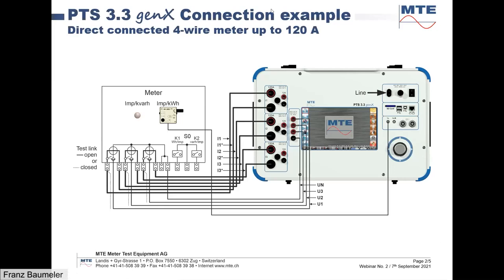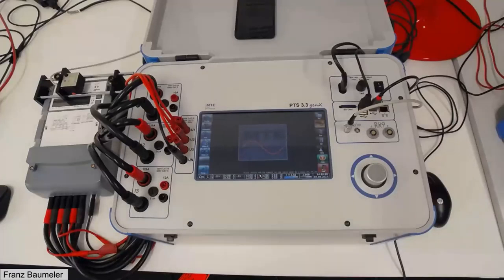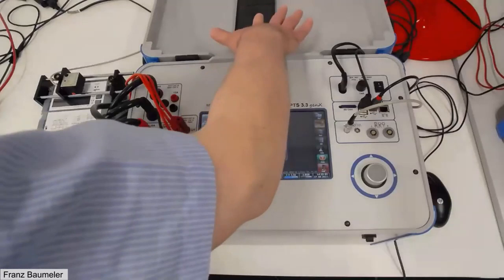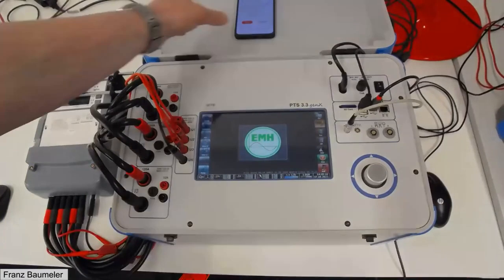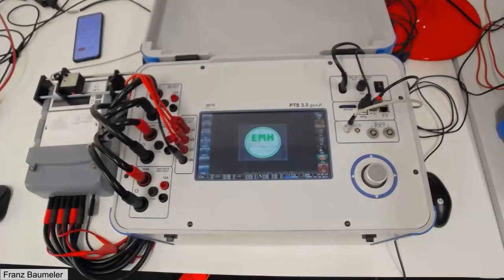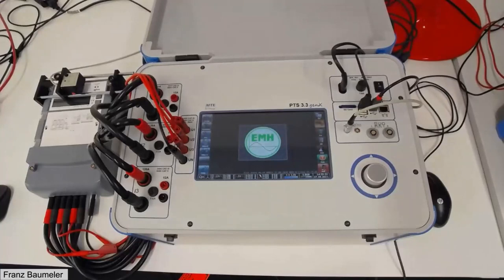Now let me change to the live view. Here you can see the real setup: the PTS 3.3 genX, and on the left side the meter connected with high current cables. The PTS 3.3 genX is a so-called portable test system, which is a combination of a three-phase four-wire current source and a three-phase four-wire reference standard class 0.05, and there is also an error evaluation system integrated with two independent impulse inputs.